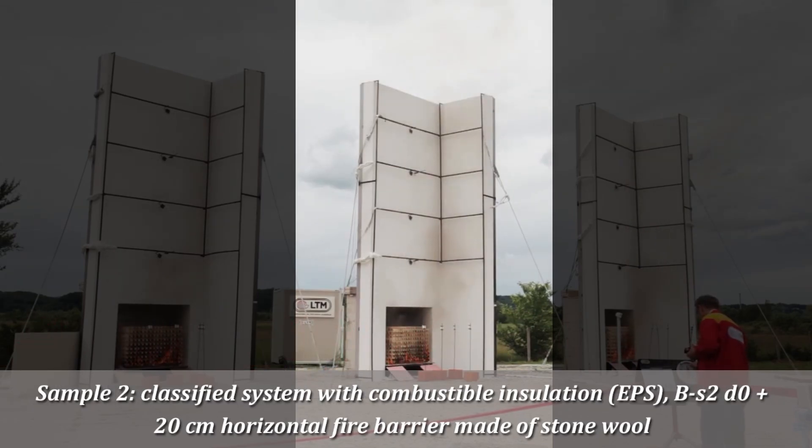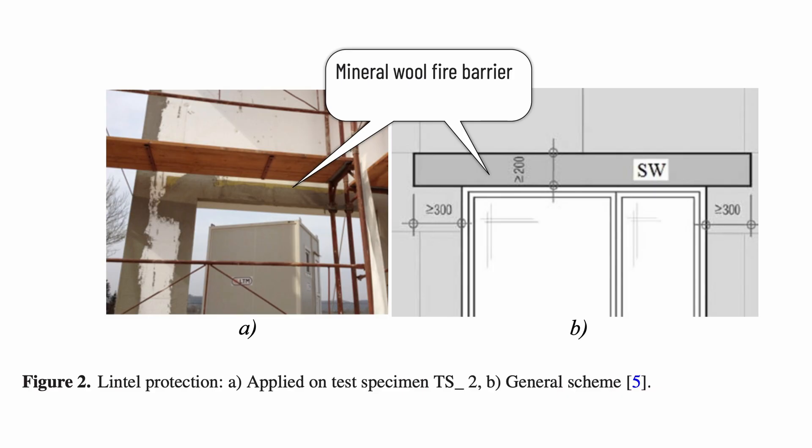The second test rig had mineral wool fire barriers installed right above the opening and at slab levels. Mineral wool is a non-combustible, A1-rated material with good insulation properties, and this barrier was sufficient to prevent the EPS insulation above from melting. Because mineral wool is non-combustible, it provided support for the cementitious coating on top, preventing flame from spreading behind the render coating above. This mineral wool fire barrier was sufficient to manage the spread of fire through the facade. However, this large-scale test is a British test and not necessarily recognized in Europe, and even in Britain it is not mandated to be carried out by system manufacturers. Current building regulations allow combustible materials on buildings lower than 11 meters, resulting in EPS insulated render being installed on 3-to-5-story buildings without mineral wool barriers above openings or at slab levels.